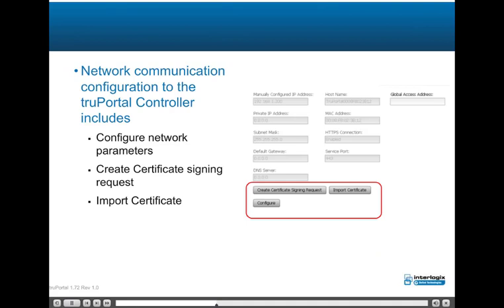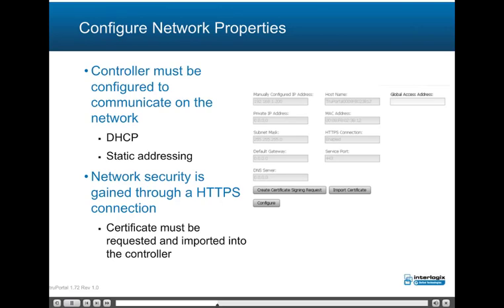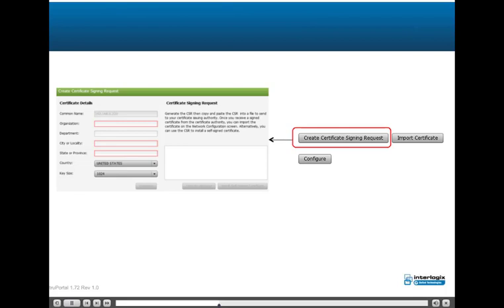Network configuration includes configuring network parameters, creating a certificate signing request, and importing a certificate. Access the Configure network properties dialog by clicking the Configure button. The controller must be configured to communicate on the network by DHCP or static addressing. Network security is gained through an HTTPS connection; a certificate must be requested and imported into the controller, and the service port may be changed but defaults to a secure 443 connection. SSL (Secure Sockets Layer) is an encryption technology that protects data transmitted between the web server and users' web browsers, preventing eavesdropping and data tampering. To enable SSL, create a certificate signing request (CSR), submit it to a certificate authority, and then import the signed certificate.